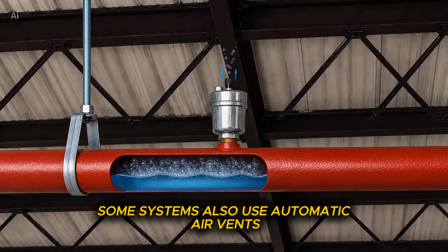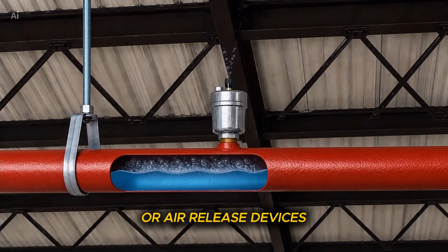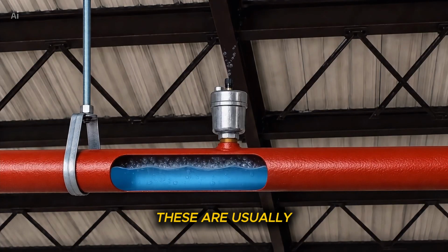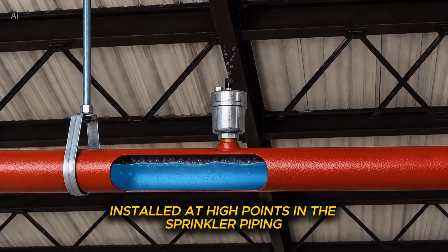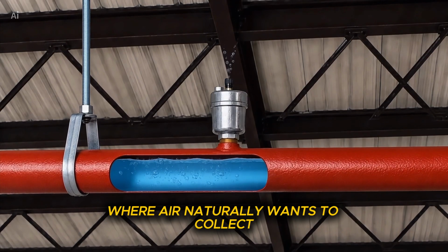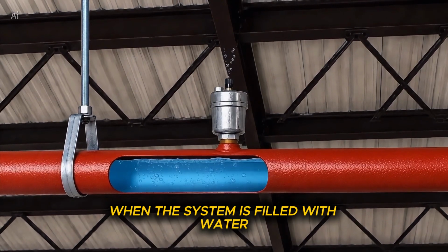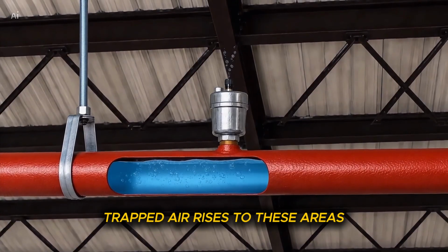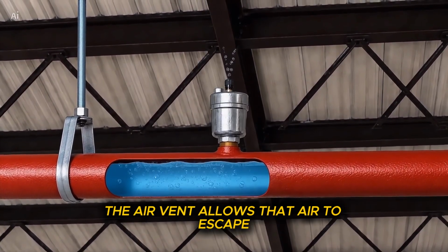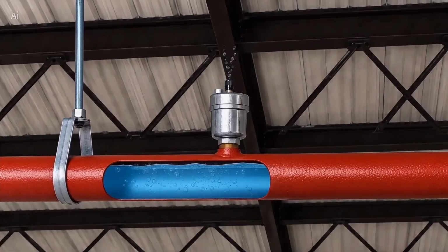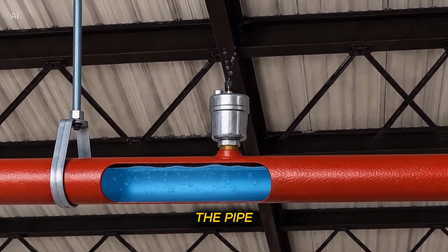Some systems also use automatic air vents or air release devices. These are usually installed at high points in the sprinkler piping, where air naturally wants to collect. When the system is filled with water, trapped air rises to these areas. The air vent allows that air to escape, instead of staying trapped inside the pipe.